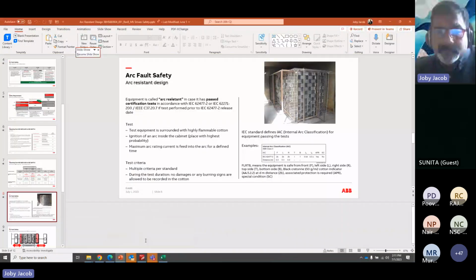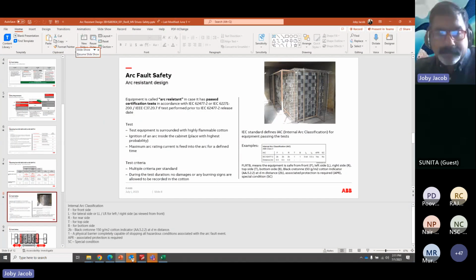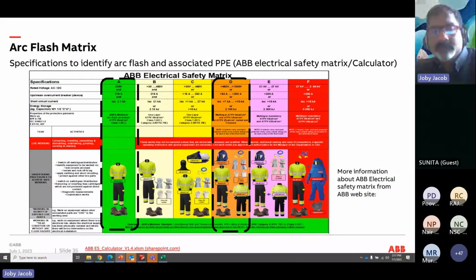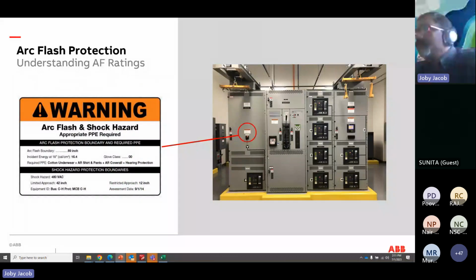Coming back to the slides, sorry. So when you do an arc flash study, based upon that, you paste an arc flash labeling, a warning. So in that label, you get the maximum arc flash boundary. So where you should stand, how much clearance distance you can have. So if you have different panels or different breakers or different feeders in a switchgear room, whatever is the highest in that is the arc flash boundary for that particular room.